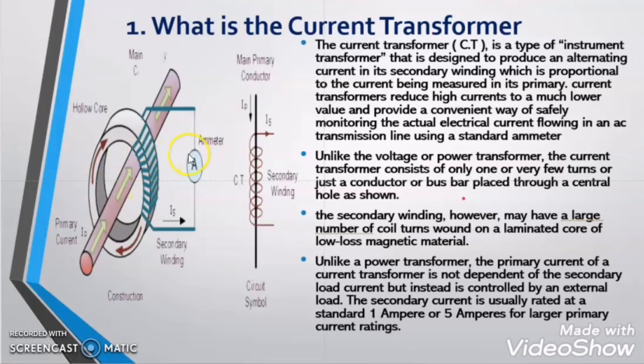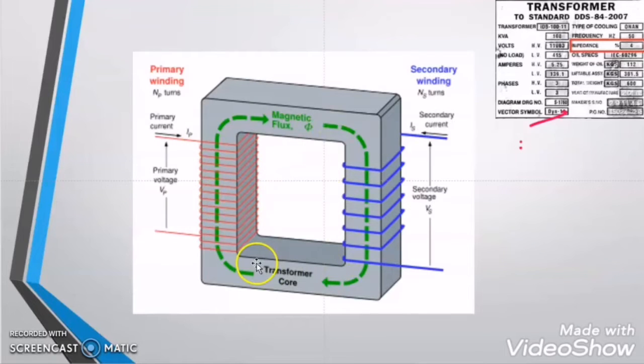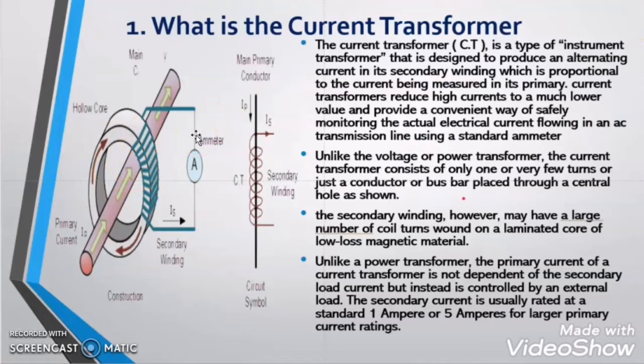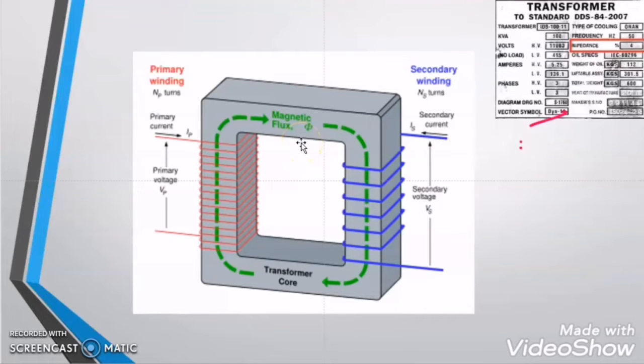There are many other differences between the current transformer and power transformer. In the power transformer it can be step-up or step-down depending on use — step-up in transmission and step-down in distribution. But the current transformer is always a step-up transformer, stepping up the voltage, or we can say stepping down the current. Also, the current transformer is used for metering or controlling electrical parameters like voltage, current, or kWh, or activating relays for protection, whereas the power transformer is used to step up and step down voltage for transmission or distribution of power.